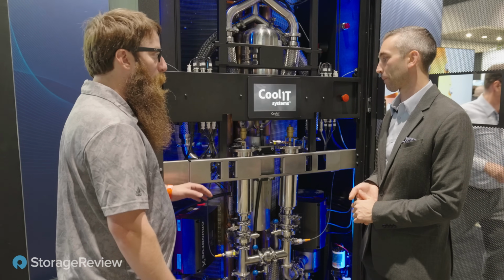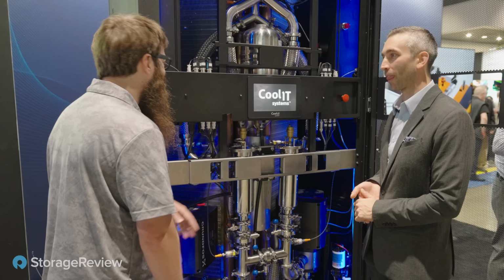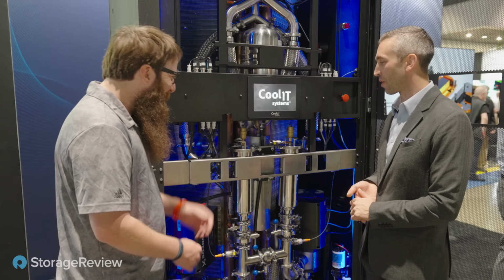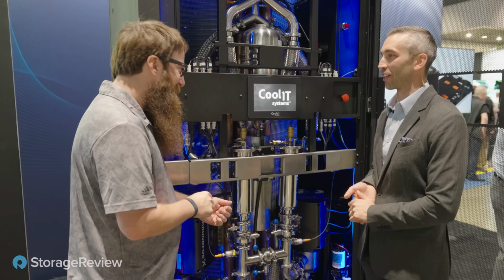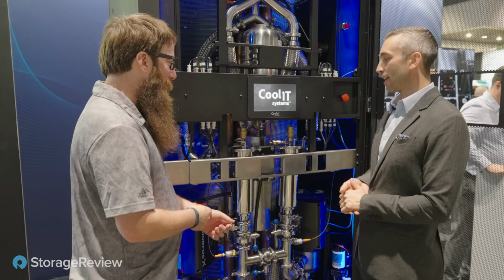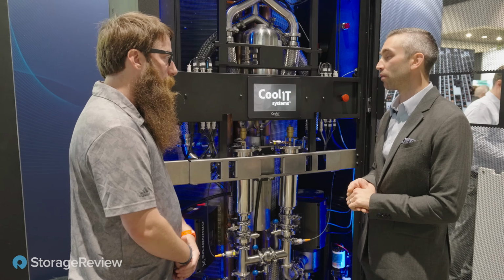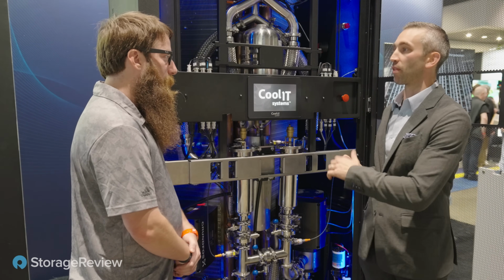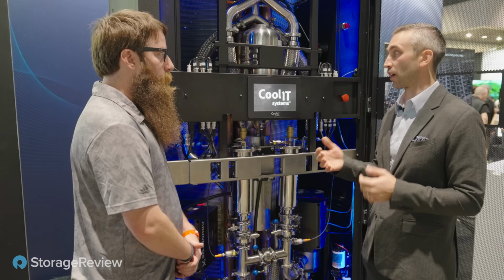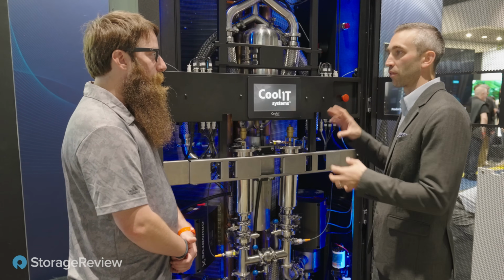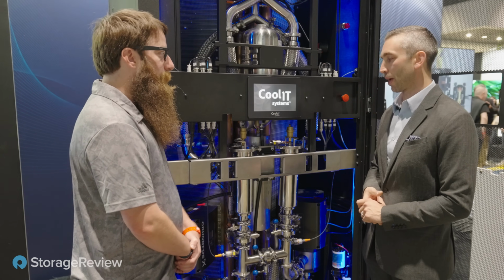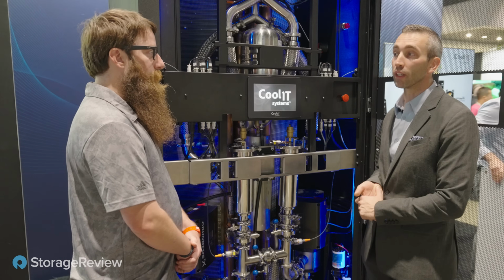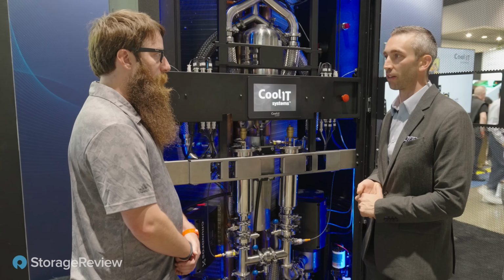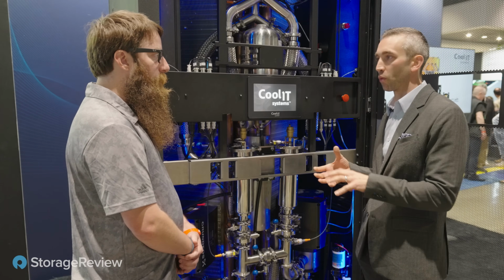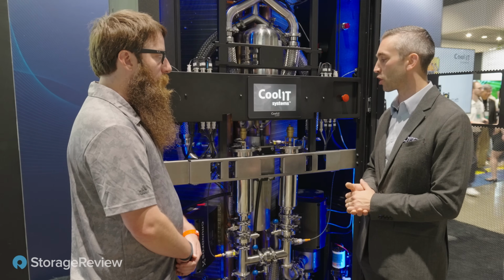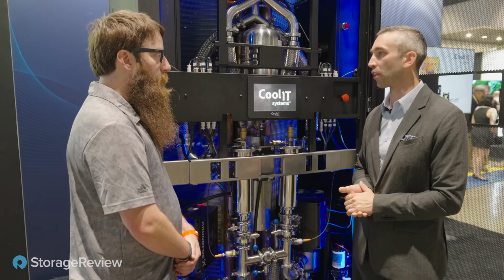So it's not pool water that's going to rust my server? No, absolutely not, don't run water without proper validation. Systems can be run with water with proper validation of the wetted materials versus the server versus the fluid. Water maintenance and quality is extremely important in liquid cooling, and if you're looking to run fluids other than what's on the recommended list, we help customers validate other fluids as well.